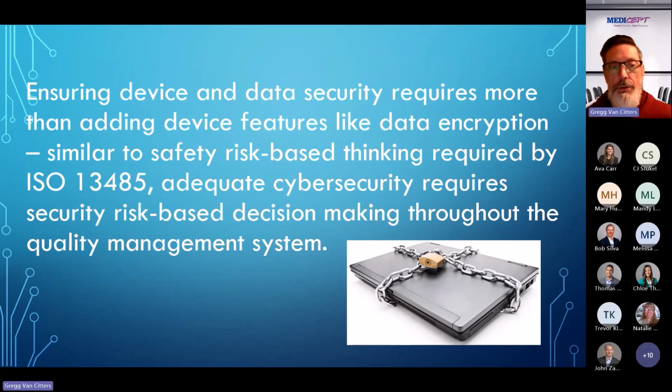But for ISO 13485, you have to embed risk-based decision-making throughout your quality management system. The whole point of a quality management system is to ensure that the medical devices and services you provide consistently meet stakeholder and regulatory requirements. Every QMS activity could either positively or negatively impact the medical device or service you provide. So you have to design your QMS processes based on the potential risk to safety and regulatory compliance, and now security as well.